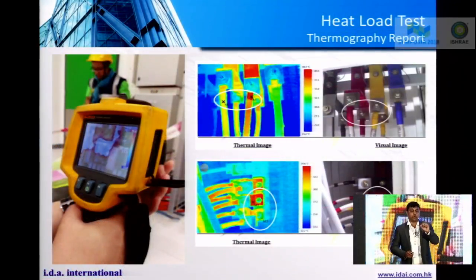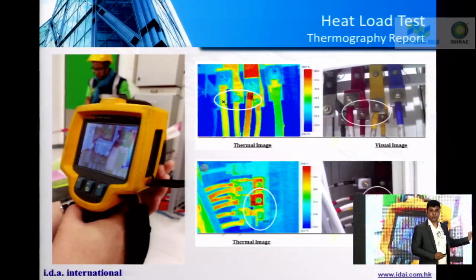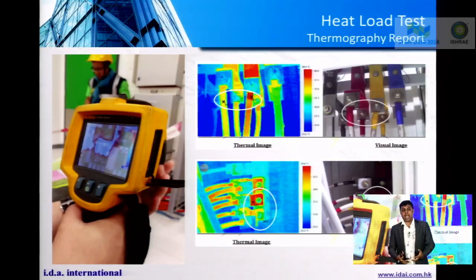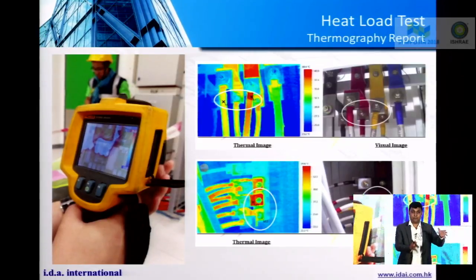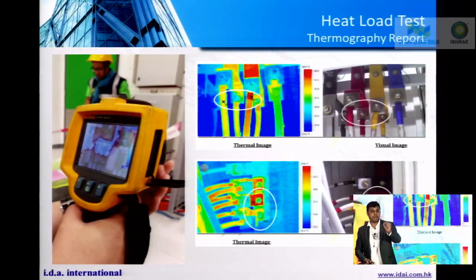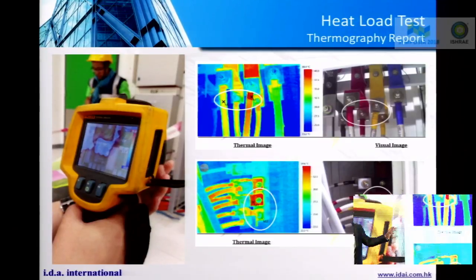Thermography. You could not get a better moment to do a thermography test for the complete MEP system. This is the right moment to do it. When you are doing the heat load test, you're actually loading the entire data hall to its maximum condition. What I can do is load my complete source A system at, let's say, 1.5 megawatts. When I'm loading my complete source A system, I'm loading my transformer, my switchgears, my UPS, my PDU to its maximum loading condition. This is the time when you can verify if there are any weak points or weak links in your system, and you can identify them through thermography.